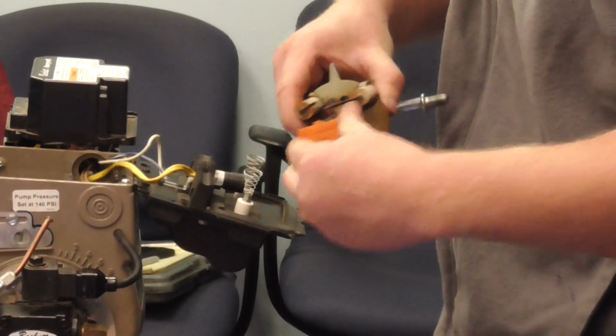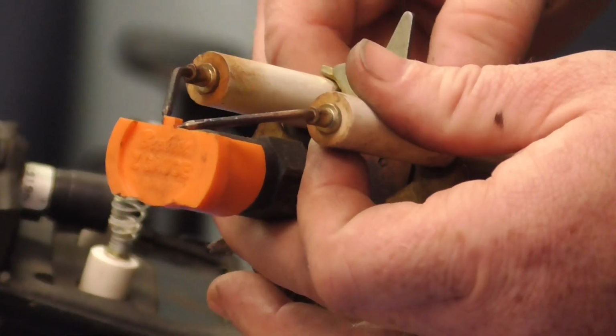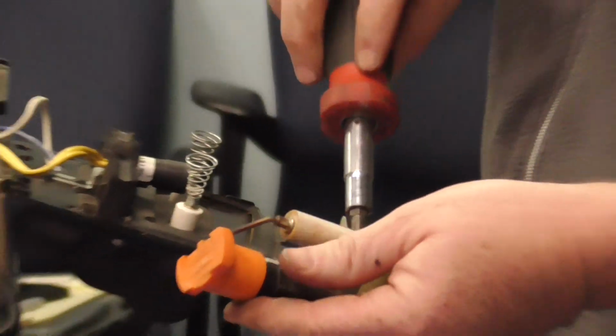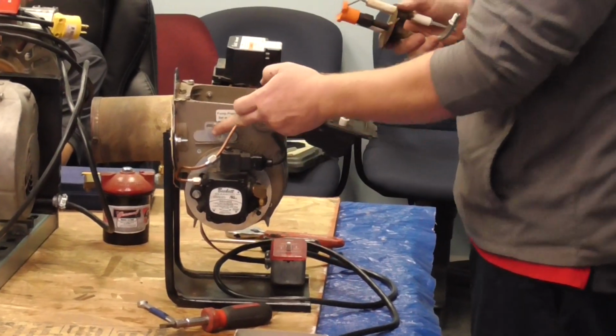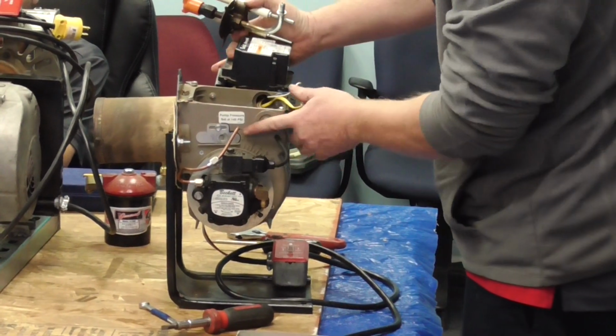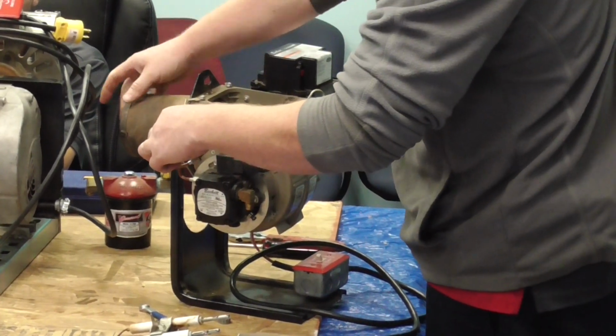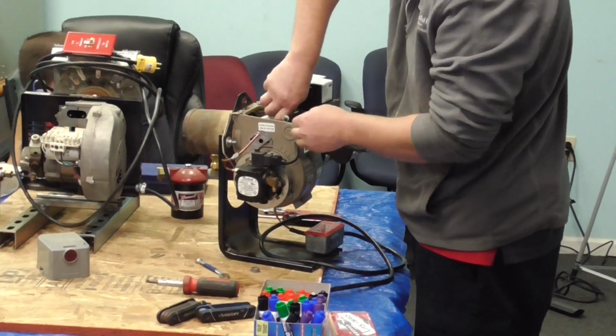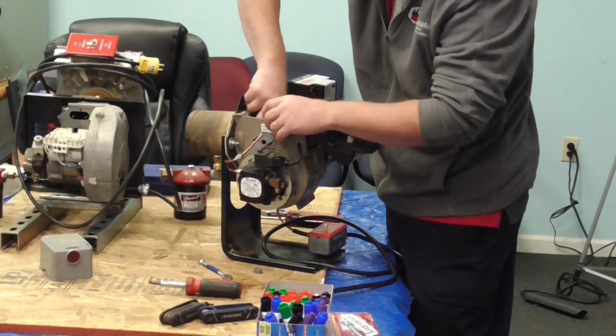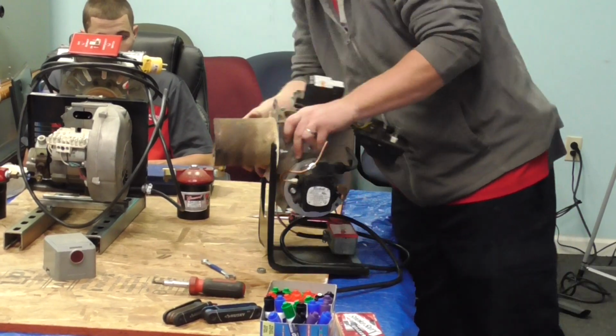After you put your new nozzle on, set that thing, just slide it on the end. Line the points up right on it, and tighten this thing down. They made it about as idiot resistant as possible. The other trick is the depth. This is what these little fins on the outside of it are for. It's got the depth behind the flame, the head of this thing. You do have to loosen that thing to get it in, and once you set that on there, it'll butt up against the face of it.